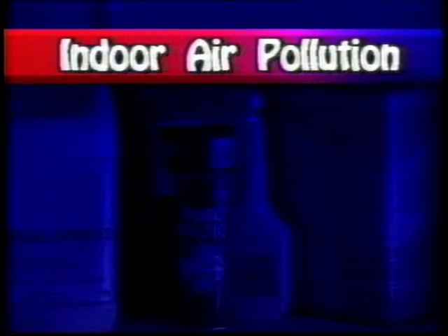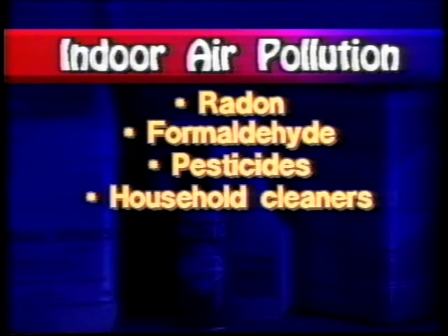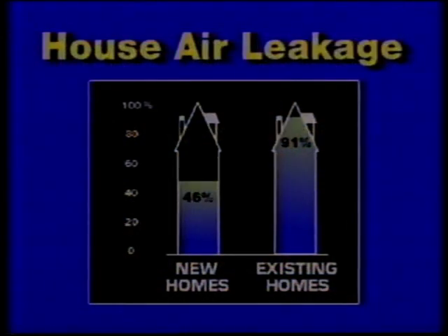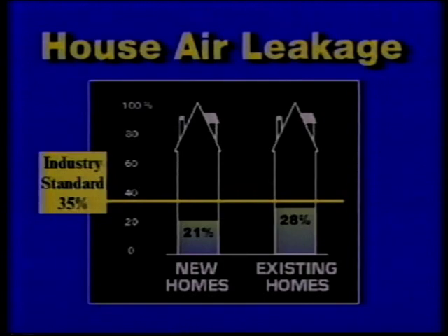Houses need to breathe because there are many sources of indoor air pollution: radon from the soil, formaldehyde from building materials, pesticides, household cleaners, paints, solvents, volatile organic compounds, and mold and mildew. When duct leaks are repaired, house ventilation rates decrease dramatically, sometimes by a factor of five or more, and indoor air quality may worsen. In a majority of new and existing homes, air exchange after repair falls below the industry minimum standard of 35% of house air per hour. It may therefore be necessary to install a mechanical ventilation system to achieve good air quality.